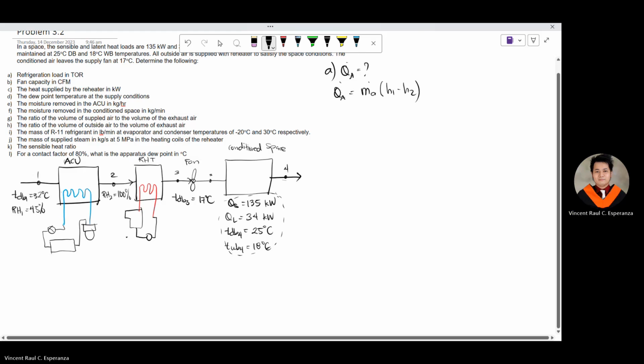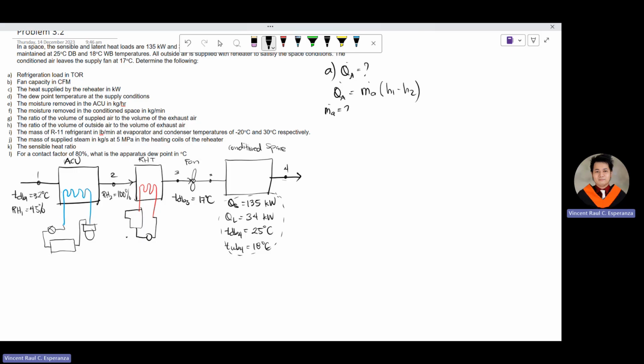To find the mass flow rate of air, let's go to the sensible heat load. We know the sensible heat load is mass of air times CP of air times TdB4 minus TdB3. In kilowatts, 135 kilowatts equals MA times CP of air, 1.0062 kilojoules per kilogram degree Celsius, times the dry bulb temperature at point 4, 25°C, minus 17°C. So what is the mass flow rate of air?